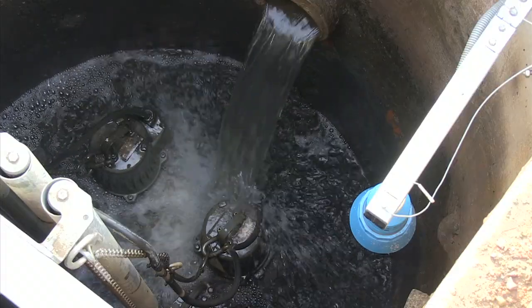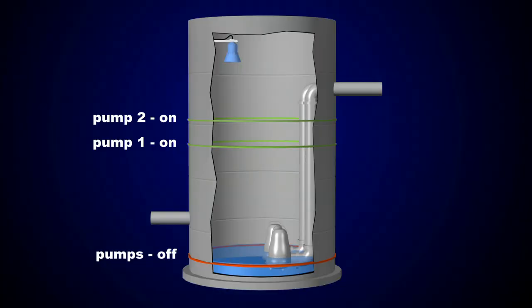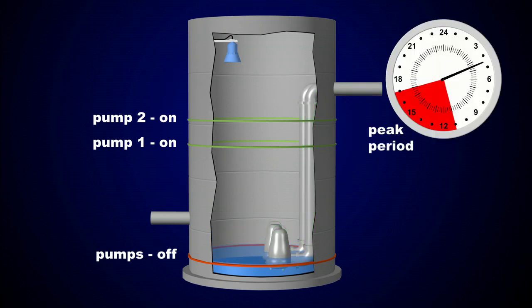The majority of Scottish water's electricity usage occurs in the wet well. A typical wet well collects wastewater until it reaches a specified high set point. The level monitor then signals the pumps to start running, and they continue to run until the wastewater reaches the low set point. It operates this way whatever the time of day or the electricity tariff rate.